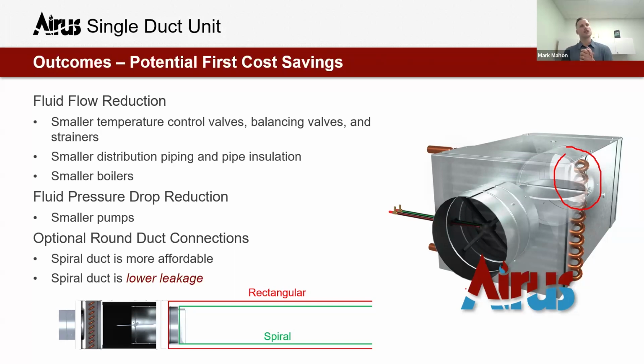Something I like to note, spiral duct is much lower leakage than rectangular duct. And when we think about a low pressure ducted system that is generally not being tested for leakage, that is generally kind of a blind spot for the system, I really like the idea as a consulting engineer being able to specify spiral duct that I know is going to be lower cost for the owner while also being lower leakage, potentially helping with operating costs and thermal comfort as well.